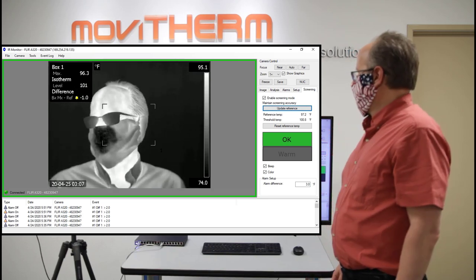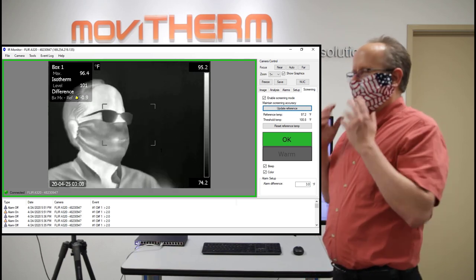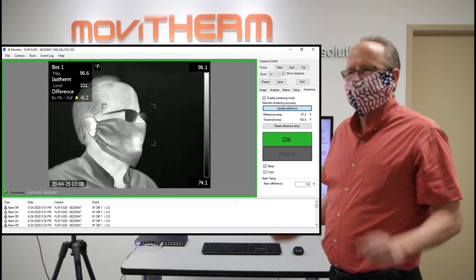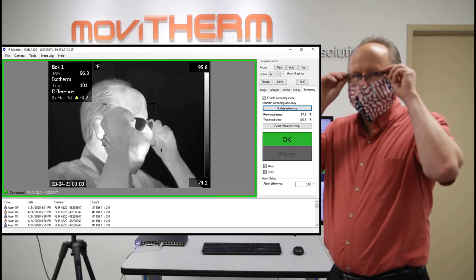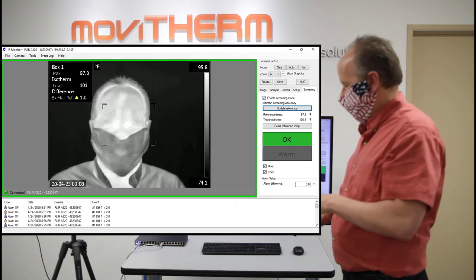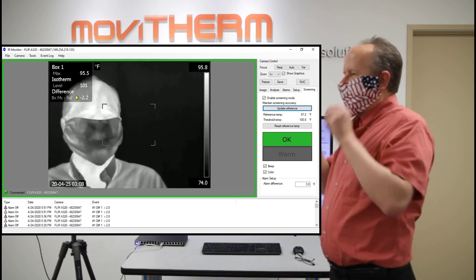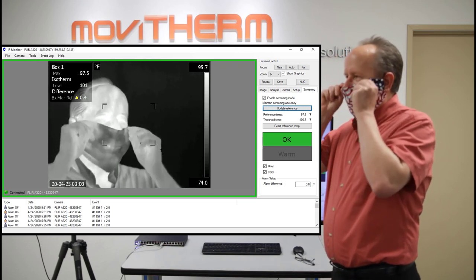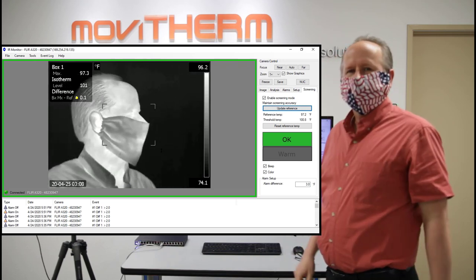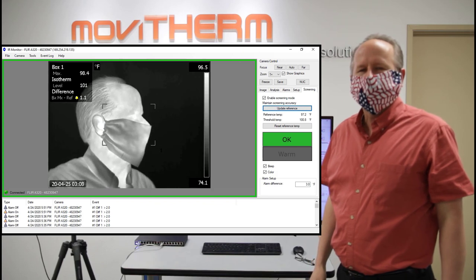You can see my glasses are extremely black, so the camera cannot see through glasses. So you need to tell people to remove the eyewear for screening because the exact temperature that is closely correlated to the inner core temperature of the body is down here in the inner tear duct area.